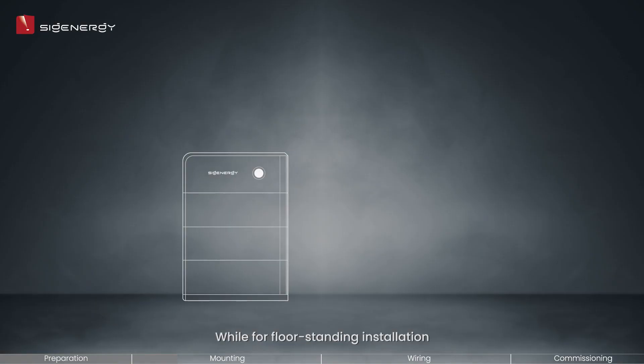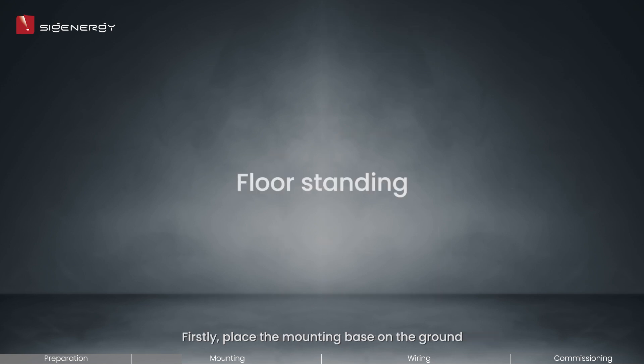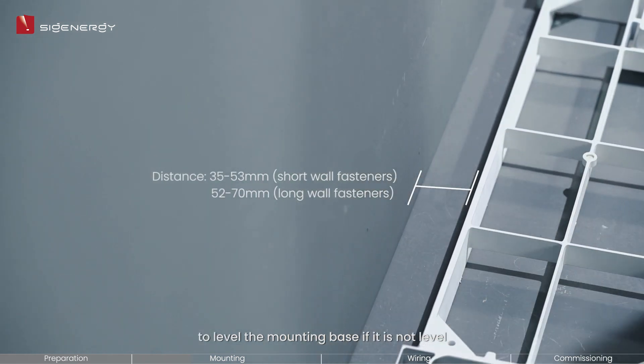For floor standing installation, no tripods are needed. Up to 6 Sigen batteries are supported for floor installation. Firstly, place the mounting base on the ground and keep a certain distance between the mounting base and the wall surface. Use a supplied leveling gasket to level the mounting base if it is not level.